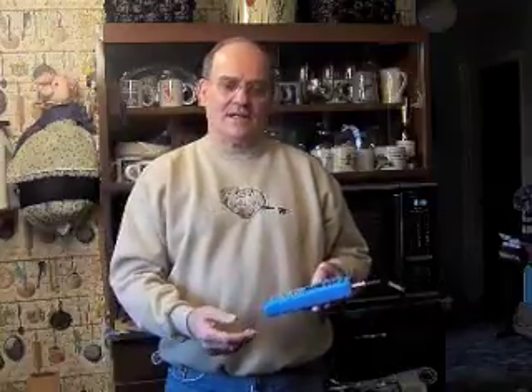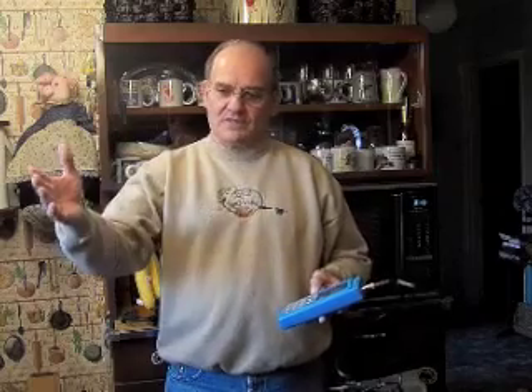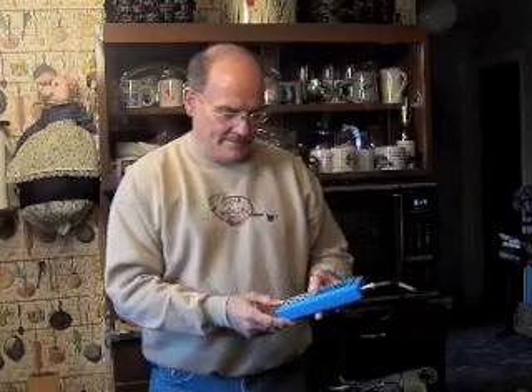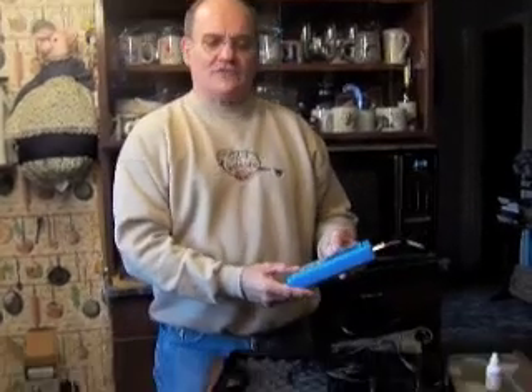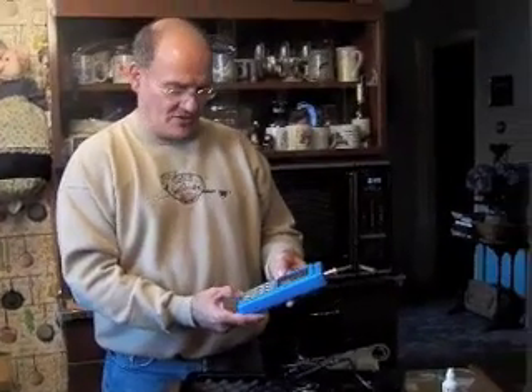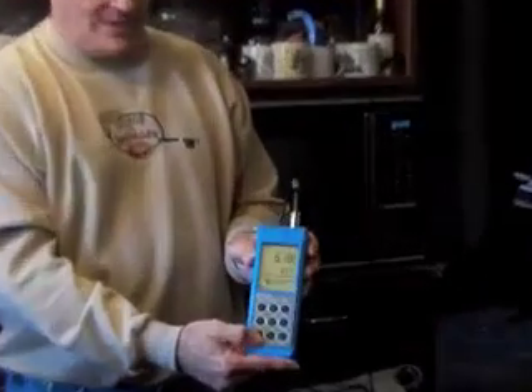Before doing a temperature calibration, you should check your meter and make sure that the automatic off feature is turned off. The meter comes with a default of 20 minutes set, so when the meter's been running for 20 minutes, it'll automatically shut off. And it takes more than 20 minutes for this meter to achieve the 2 temperatures that you need, the temperature near 0 and 50 that we're going to do, the 2-point temperature calibration. So you want to shut the auto off feature off completely on the meter. The way you do that, usually when you're trying to change a feature, you want to hit that setup button in the lower left corner.